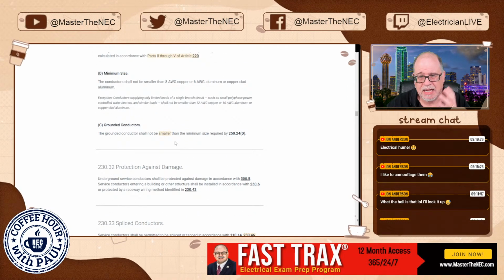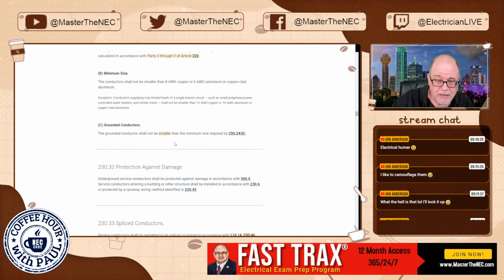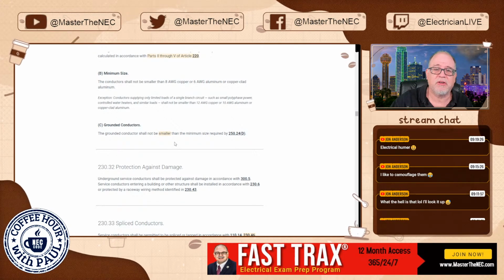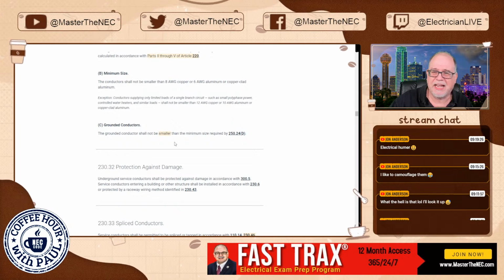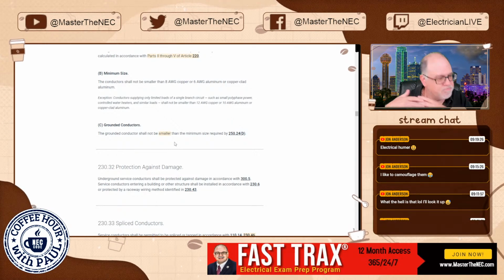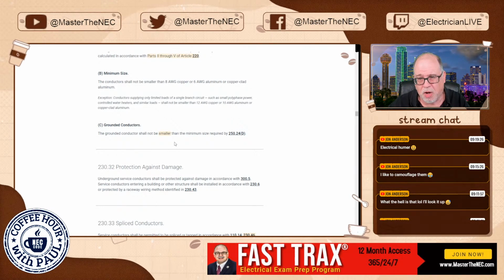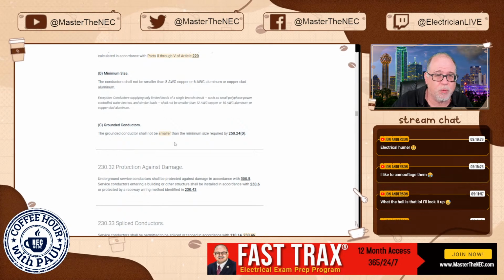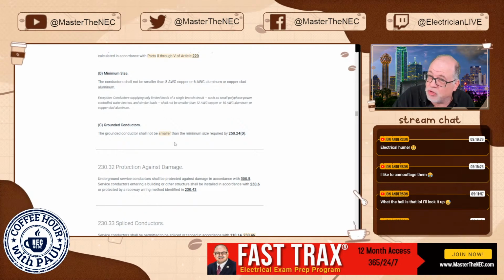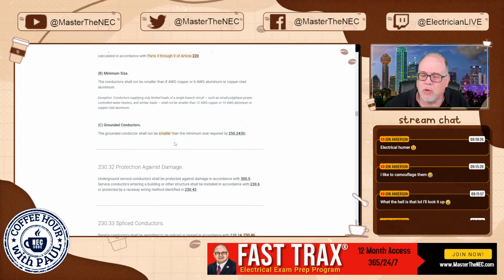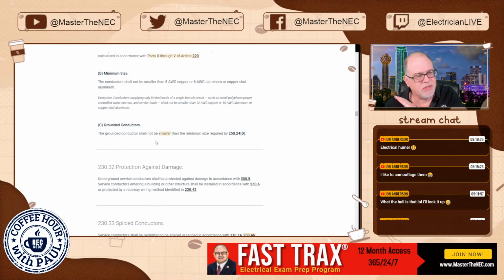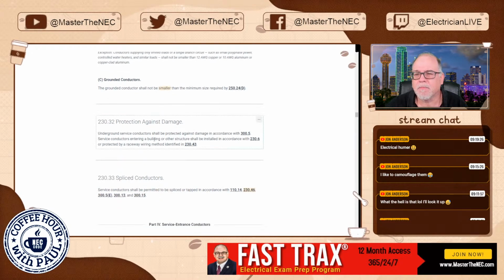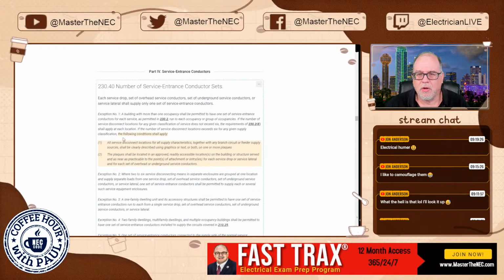So, not smaller than. Now, could it be larger? Absolutely. You still got to do a load calculation for the grounded conductor. It's got to handle the maximum imbalance load. You still got to do that, but it can't be smaller than what's described in 250.24(D), and ultimately that's going to send you where? 250.102(C), okay? There's a little nifty table there. All right.